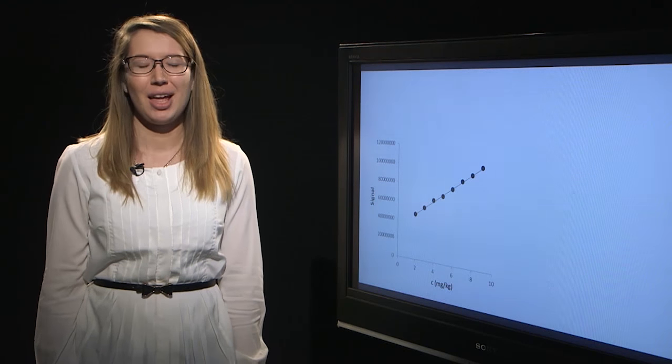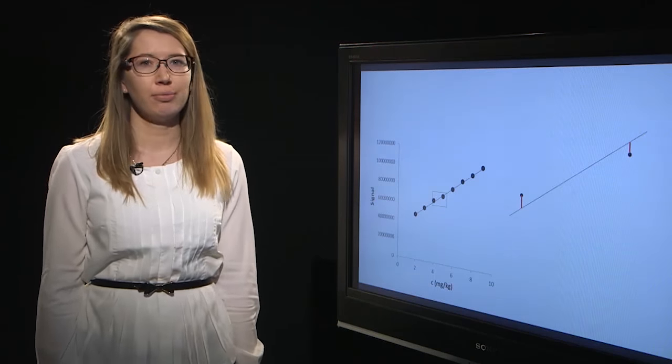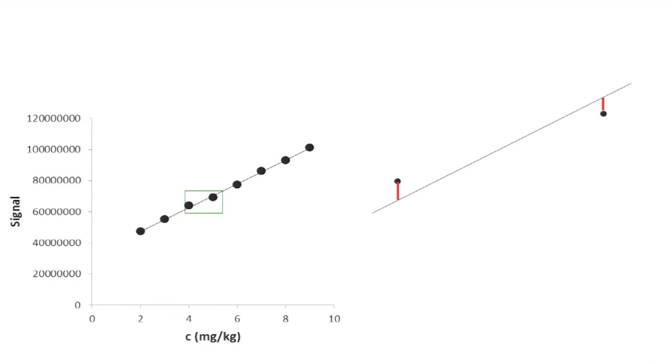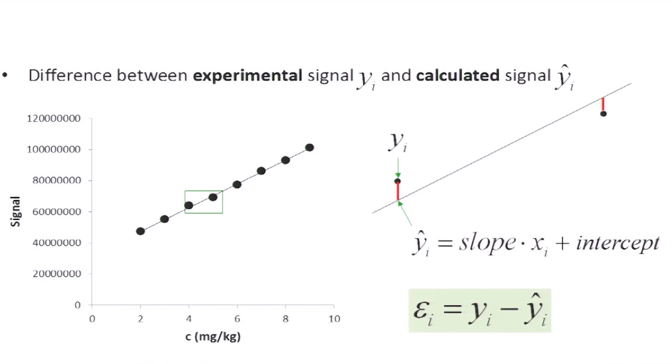What does this mean? When we take a closer look of our calibration graph, we see that there is a difference between the experimental signal we get from our measurements and the calculated signal we get from the calibration function describing our calibration model. And this difference between the experimental signal and calculated signal is defined as the residual.